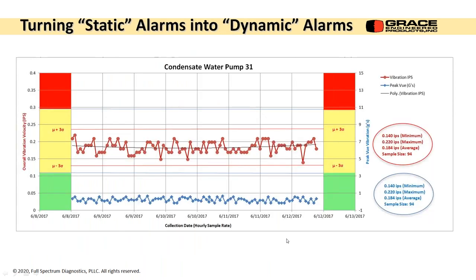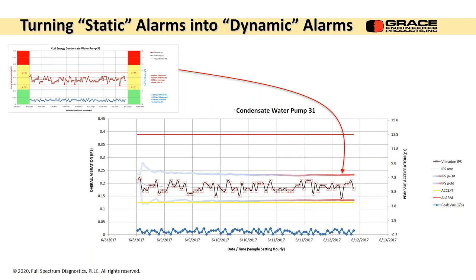Okay, this data is the starting point. I have some alarm levels that are mean plus 3 sigma. It's based on the real data, and it's just statistics. This is where the alarm probably will occur. This was a plot of regular vibration velocity, which are the red dots, and this scale is acceleration, so it's PeakVue. It's an ultrasonic measurement, with some of the stats on that. But this is what you can do with the single point wireless transducer. You can take that data, and this was 94 measurements, 1 an hour. And I can see massive statistical changes.